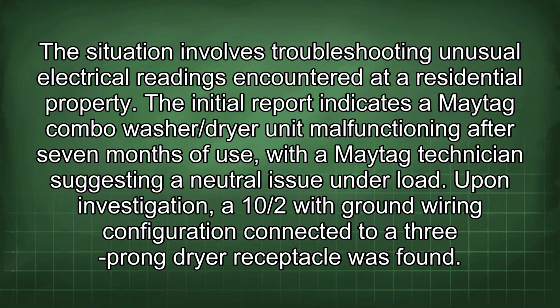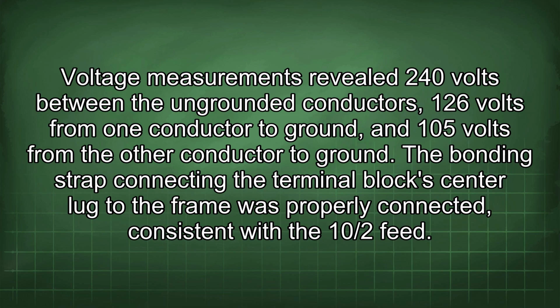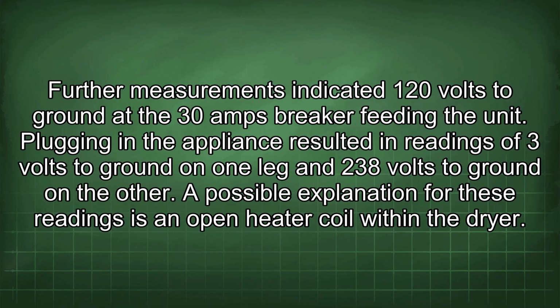Upon investigation, a 10/2 with ground wiring configuration connected to a 3-prong dryer receptacle was found. Voltage measurements reveal 240 volts between the ungrounded conductors, 126 volts from one conductor to ground, and 105 volts from the other conductor to ground. The bonding strap connecting the terminal block center lug to the frame was properly connected, consistent with the 10/2 feed. Further measurements indicated 120 volts to ground to the 30 amp breaker feeding the unit.